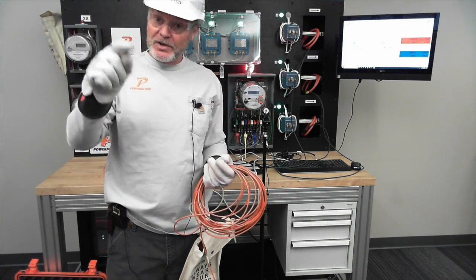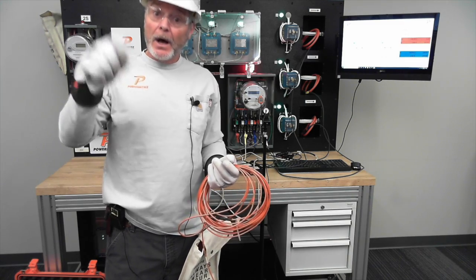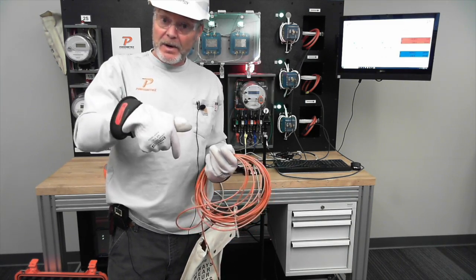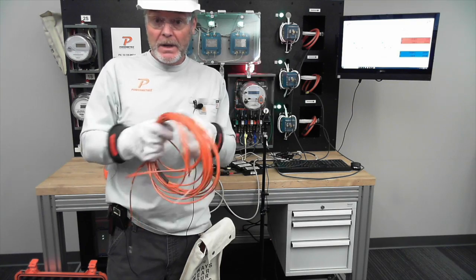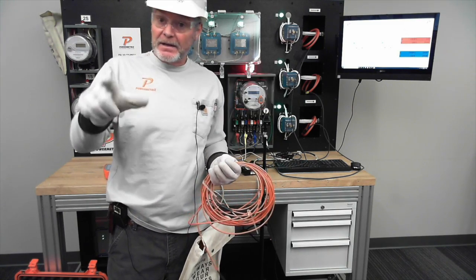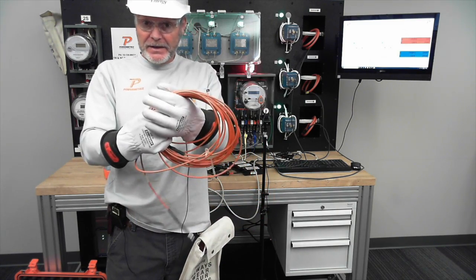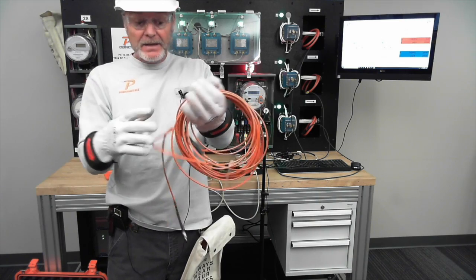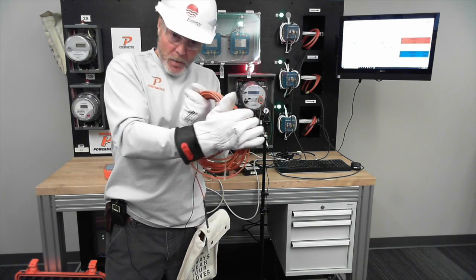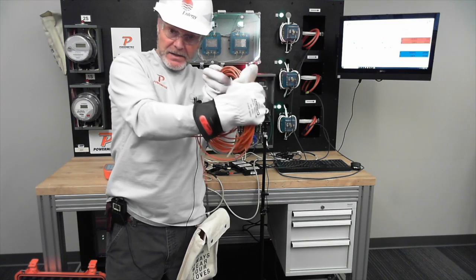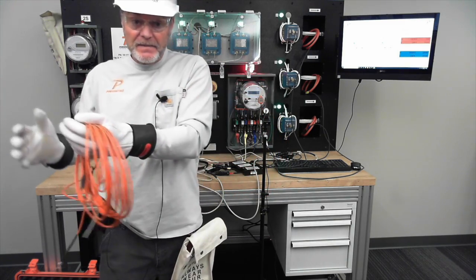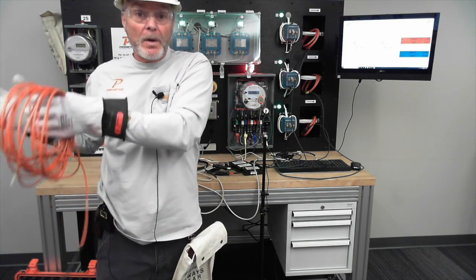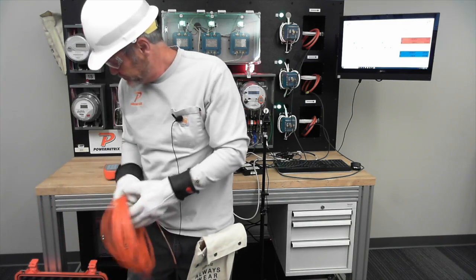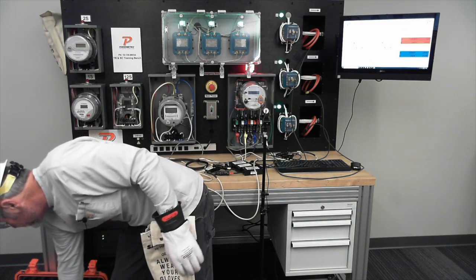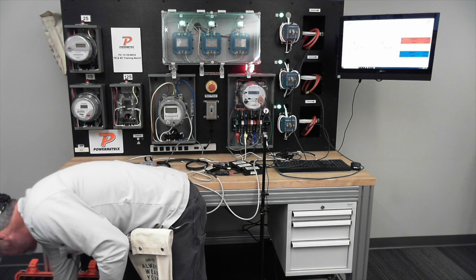So if you do decide to go coax, always give us your coax cable to calibrate your HighVolt probe, because with those losses, we're going to need to calculate those in when we get ready to calibrate your test probe. So fiber is more expensive but no losses; coax is less expensive but you will experience some losses with a longer cable. To be clear, you should not experience any loss with coax under 100 feet.